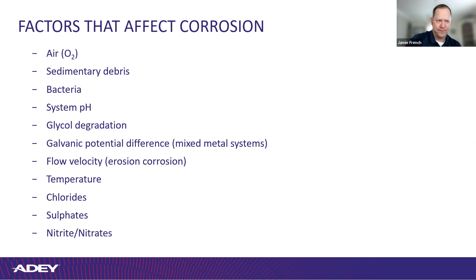And then flow velocity, that's Antonia's favorite, erosion corrosion. She likes rhyming. She's a poet and didn't know it. But yeah, you can cause leaks on elbows, right, when you're flowing too much and there's debris in that system. And then the final ones are typical chemistry of water. Just temperature can help affect corrosion, and chloride, sulphates, and nitrates are contributors to that bacterial infection in the system.